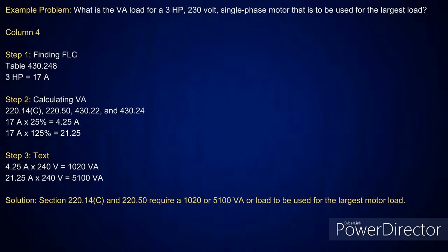Okay? But that's something I want to take a little bit of a look at, because I look at it this way. People say, well, that's a motor load. Well, you could say that you want to calculate it like that. But when you're really getting into that, I don't look at it that way, because that is an assembly. It's not something that's separate. So I would look at that if all of them are being continuous, just like lighting loads. And I could even have a receptacle, you're plugging something in that's individual and operates 3 hours or more. Those will be taken at 125%. But I'll go over all that when we get into commercial.